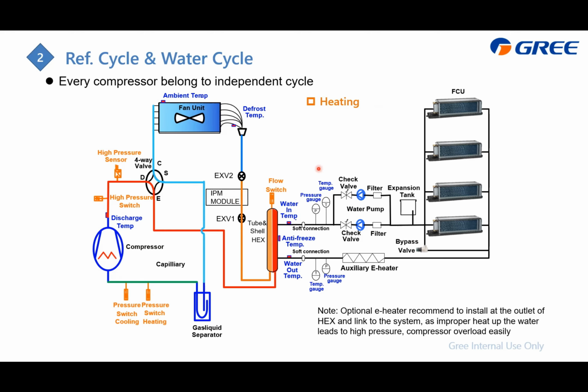As for the water cycle, this time there is no change, which means we don't change the direction. The water from the water pump will flow to the heat exchanger. After heating up, it will become warm or hot water. Then we make this hot water flow to the FCU to release heat, which is doing heating. Then this water will be cooled down and flow back to the water pump.